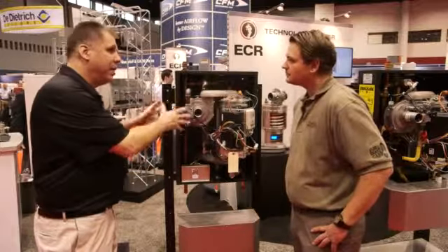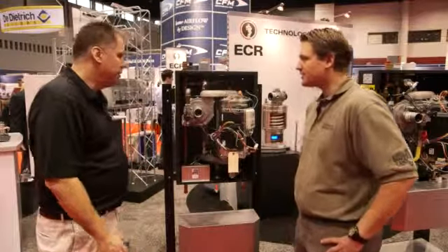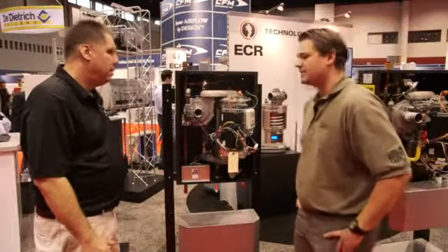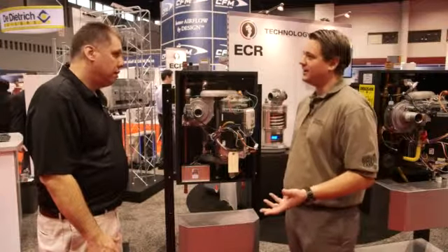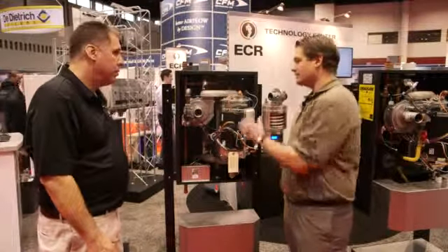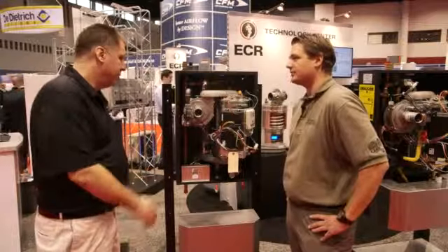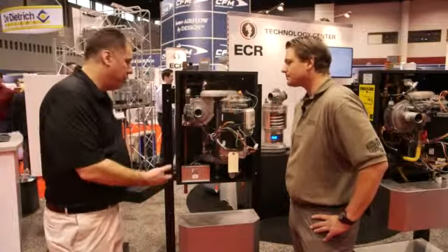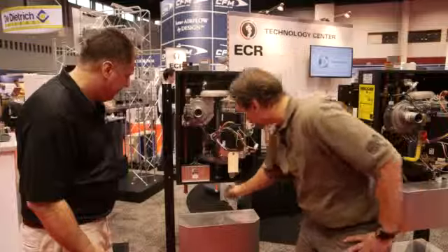So this is going to be a residential, maybe light commercial. Another application for it is if you had a boiler that already had primary, secondary, and you're up to replace it, this is a great option for you to replace it. Simplifies the piping. How about the condensate? Where do I drain the condensate on this? The condensate drains out of the bottom.